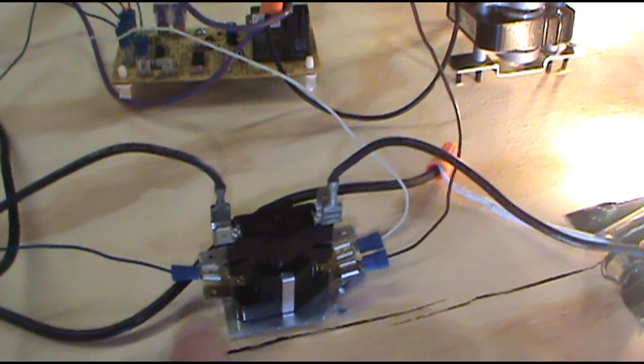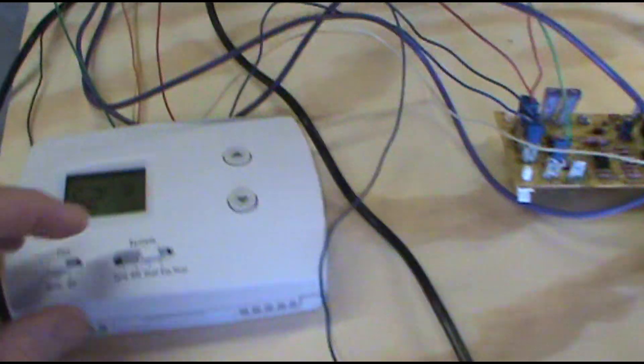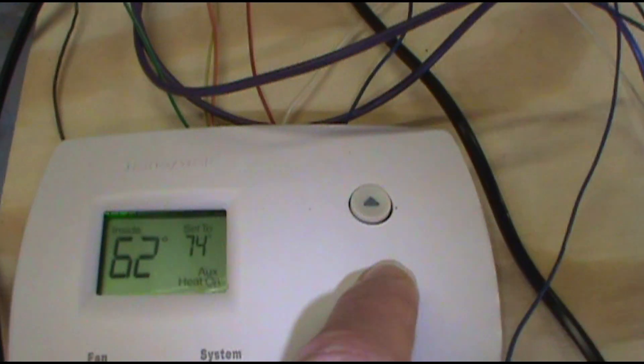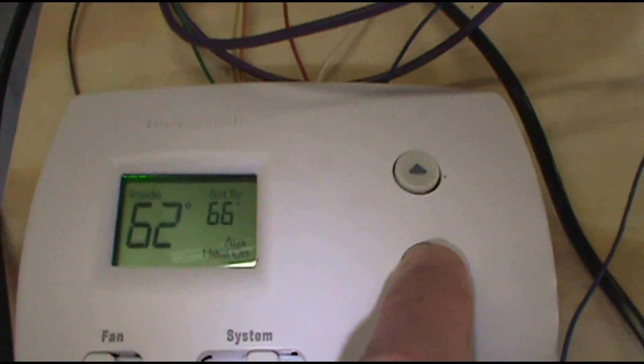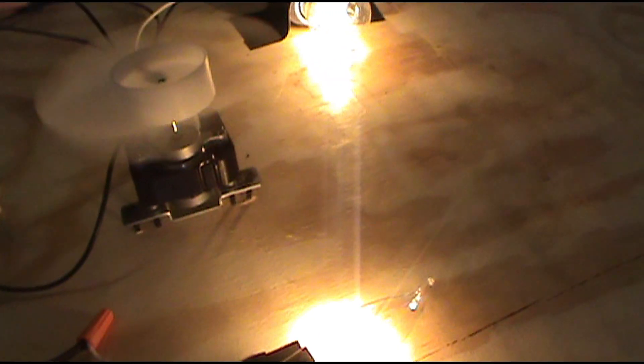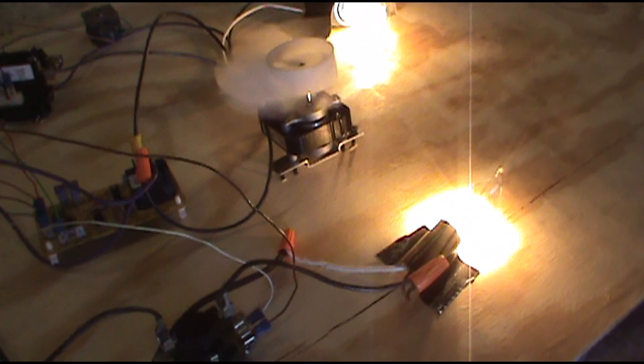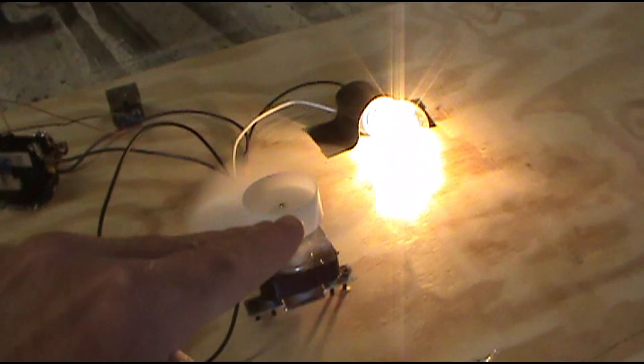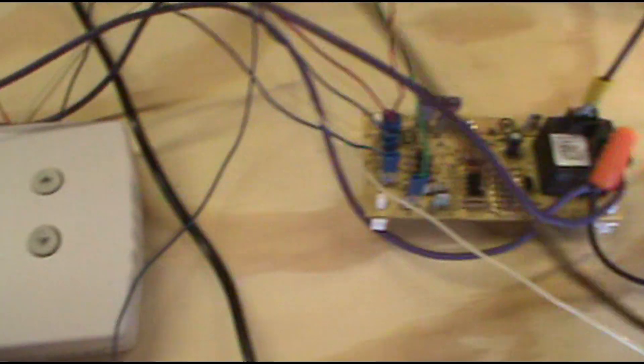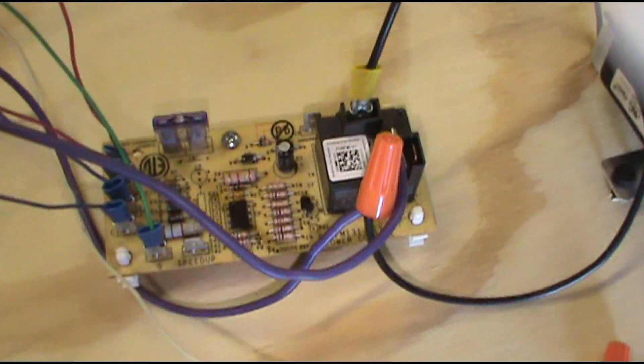There we go, now our heat strips are on. So condenser and heat strips are now working together. And you can get your meter and probe around on here, do some experimenting. Now if you set the thermostat down to a degree above, you're going to kick the heat strips off but the condenser will stay on. Our light bulb over there, that's the condenser. There we go, it no longer needs auxiliary heat and the condenser is handling all the heating.